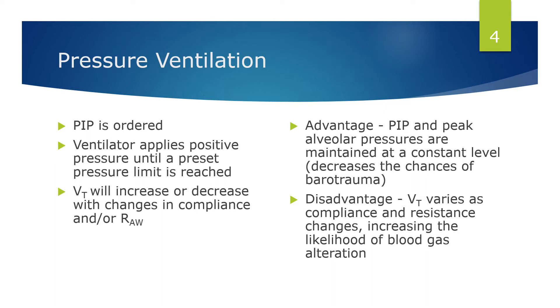The advantage of pressure ventilation is that peak pressures and therefore alveolar pressures are maintained at a constant level, so there is less chance of barotrauma. The disadvantage is that because tidal volume will vary, that changes minute volume, which changes CO2 removal — so you will have blood gas value alterations.